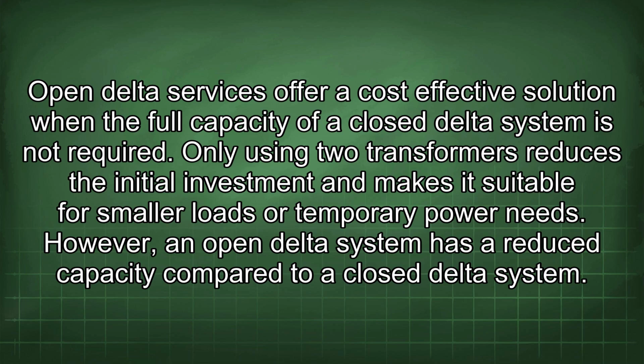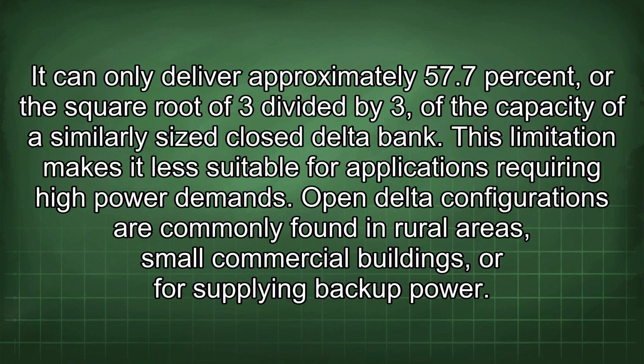However, an open delta system has a reduced capacity compared to a closed delta system. It can only deliver approximately 57.7%, or the square root of 3 divided by 3, of the capacity of a similarly sized closed delta bank. This limitation makes it less suitable for applications requiring high power demands.